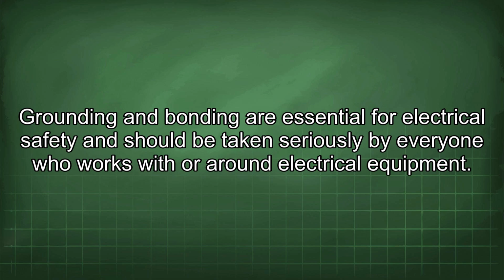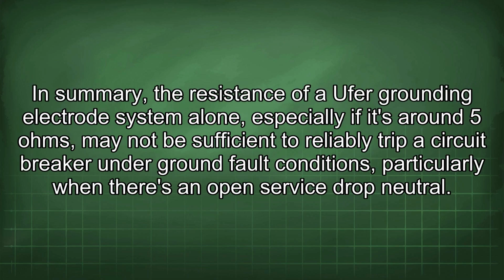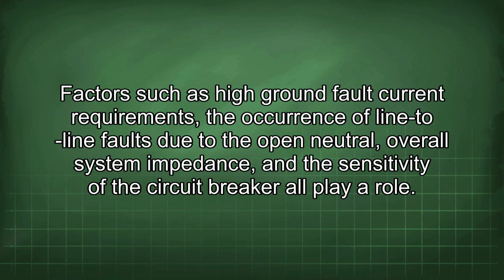In summary, the resistance of a Ufer grounding electrode system alone, especially if it's around 5 ohms, may not be sufficient to reliably trip a circuit breaker under ground fault conditions, particularly when there's an open service drop neutral. Factors such as high ground fault current requirements, the occurrence of line-to-line faults due to the open neutral, overall system impedance, and the sensitivity of the circuit breaker all play a role.